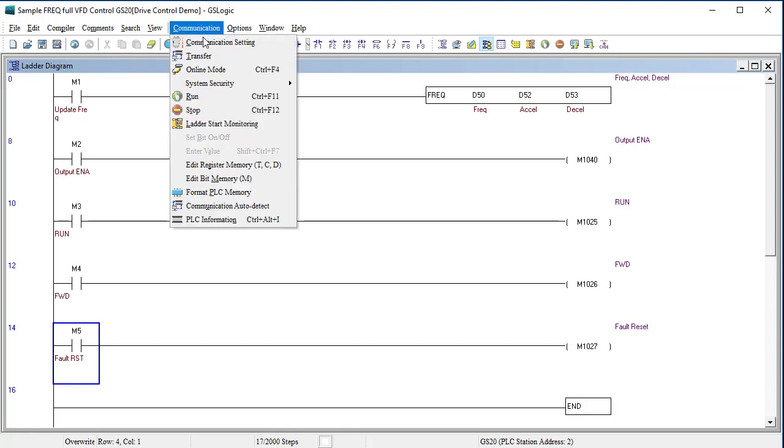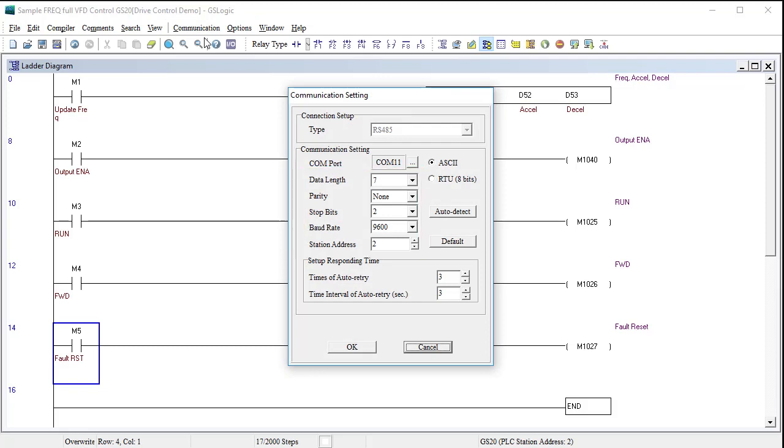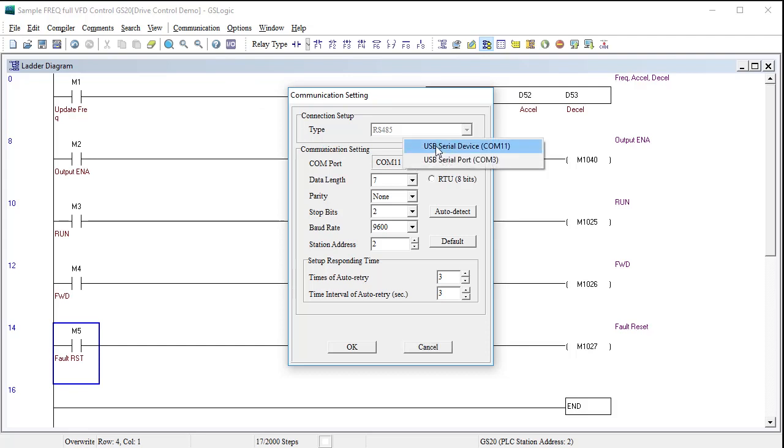Go to the communication menu to set up the COM port. Since the GS20 uses the dedicated USB configuration port, you don't really care about these. We just need to make sure we are using the correct COM port, which we know from the previous videos is COM 11, and that we are using RTU.